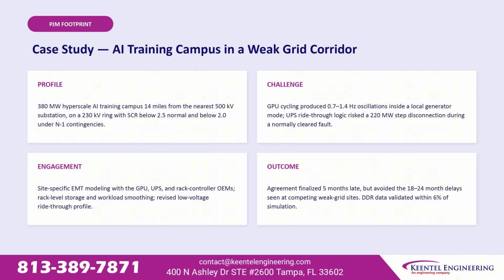Our first case study, a 380-megawatt AI training campus 14 miles from the nearest 500 kilovolt substation, sitting on a weak grid with a short-circuit ratio below 2.5 normally and below 2 under contingency. GPU cycling produced oscillations landing right inside a local generator mode, and the facility's backup power logic risked a 220-megawatt step disconnection during a normally cleared fault.